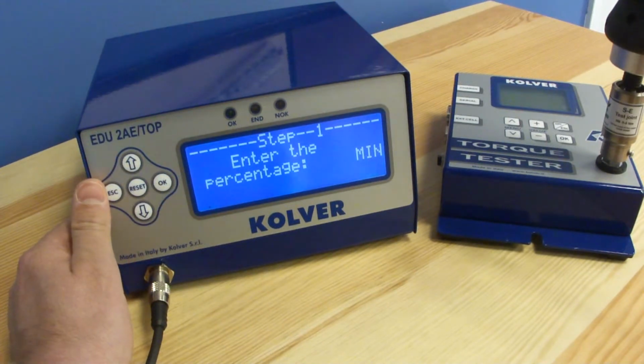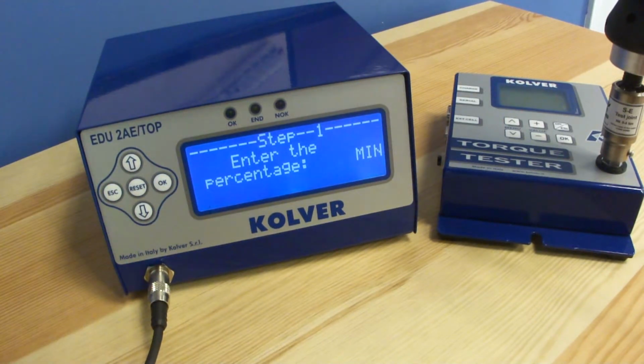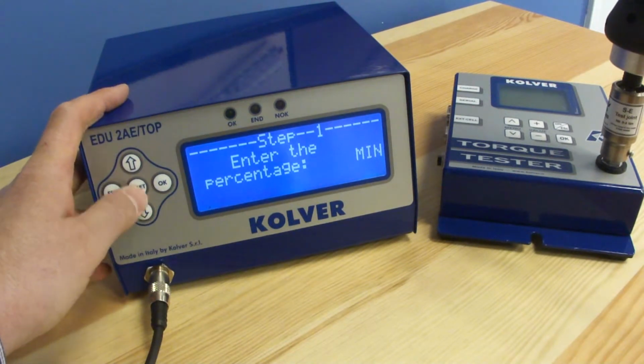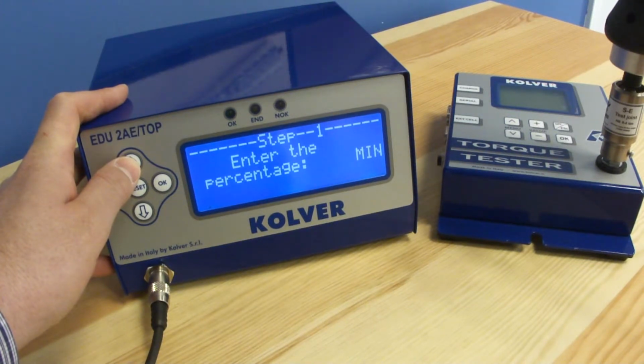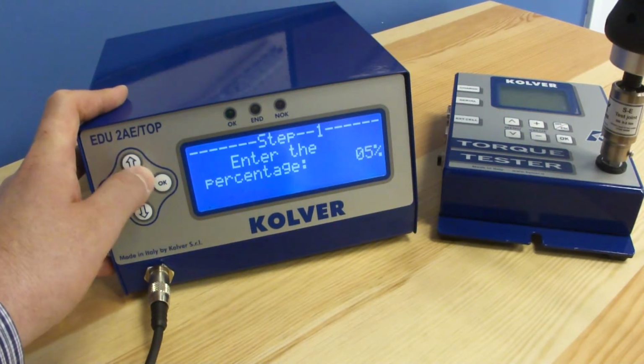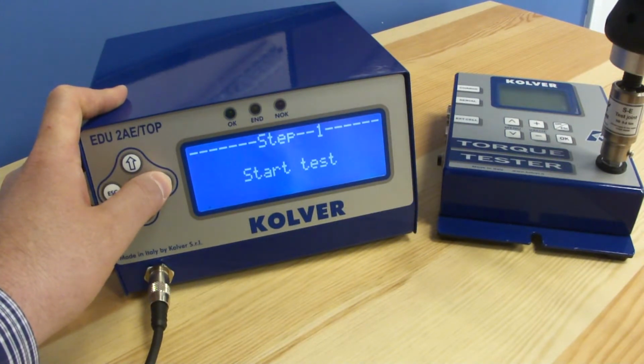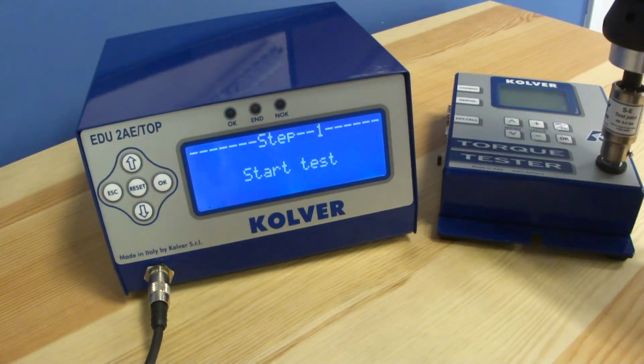It's going to ask us to enter a minimum and maximum percentage of torque. The reason behind this is that since this is a current controlled system, we're teaching the controller how to accurately read the torque reading on our calibrated torque tester. It's recommended that we go with a 5% to 10% window above and below our target torque. In this case, where we're set at 10% of our target torque, I want to enter 5% for the minimum. It's going to ask us to start our test.